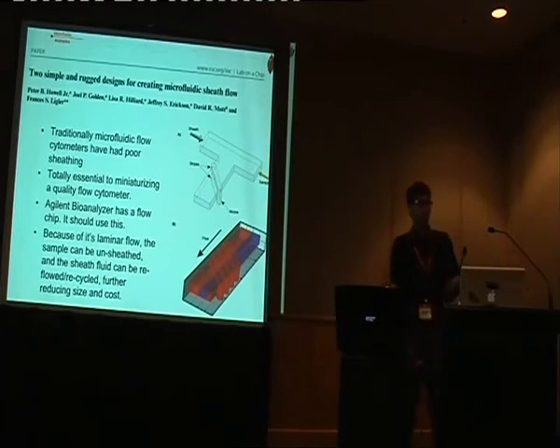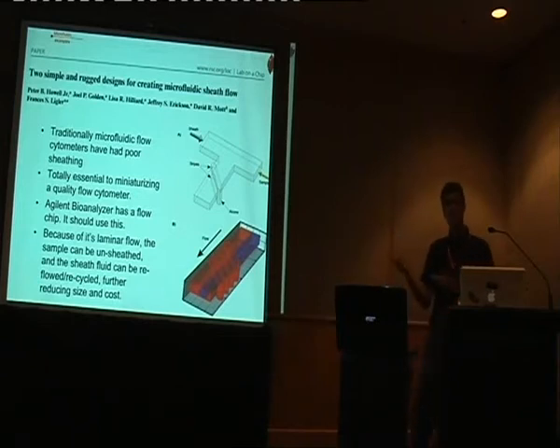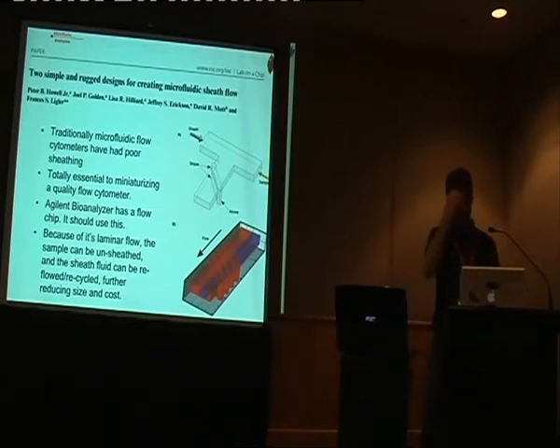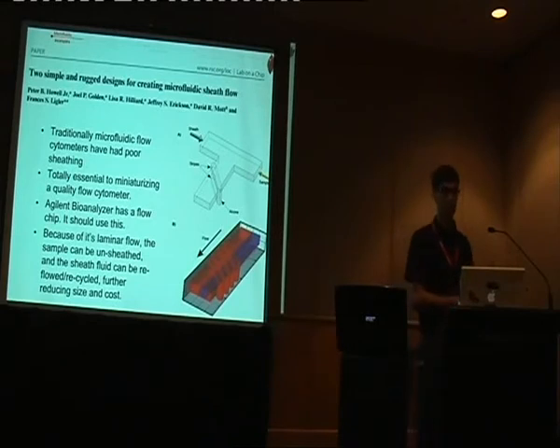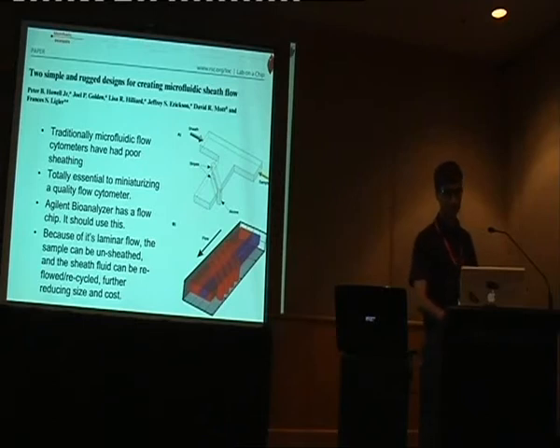Normally when you run flow cytometry, you have to run about a liter of saline per hour — and if you want to make a portable device, you can't lug liters of things around. With this system, you can recover 90% of your sheath fluid and just keep recycling it. I think these two things are really key if you want to make a small flow cytometer. I suspect the Agilent Bioanalyzer chip, if it survives another five years, will probably use this technology.